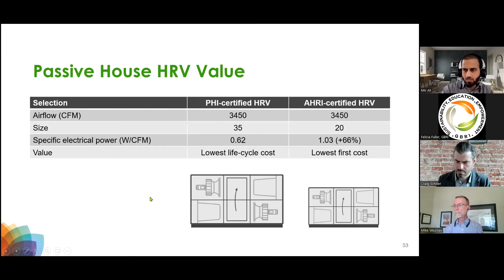Here's an example, for a school project in New York. We were asked what the difference is between a passive house ERV and an ERV selected to meet code. The difference is the size. In passive house, we routinely pick a larger size that meets that 0.765 watt per CFM requirement. By increasing the size of the unit, yes, you add some cost, but you dramatically reduce the life cycle cost and reduce your energy bills from day one. It becomes a life cycle cost product selection.